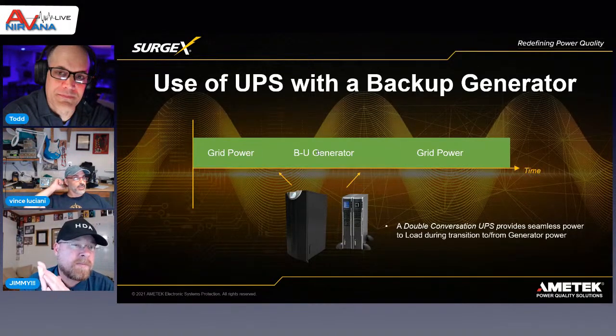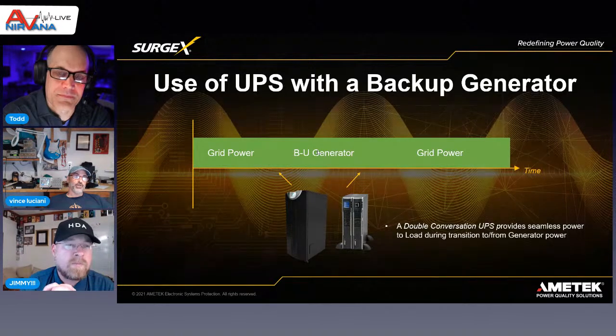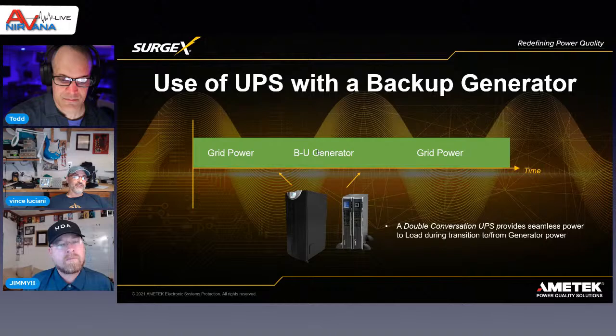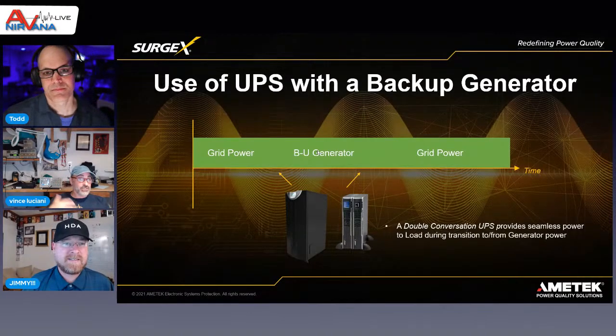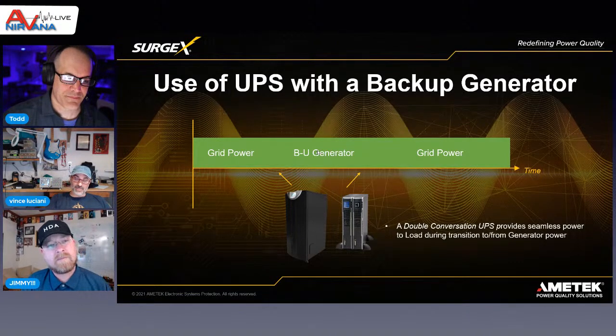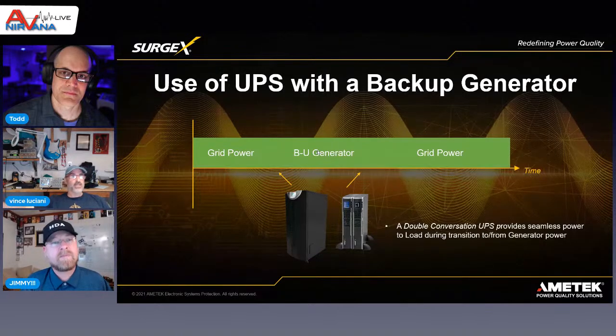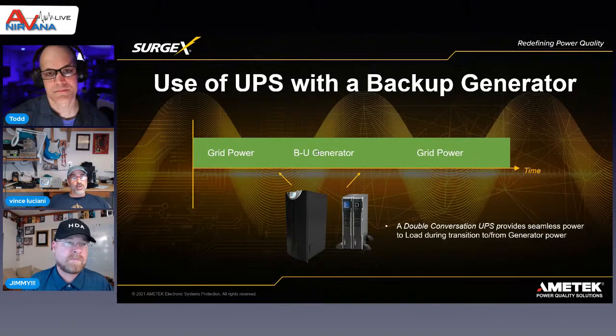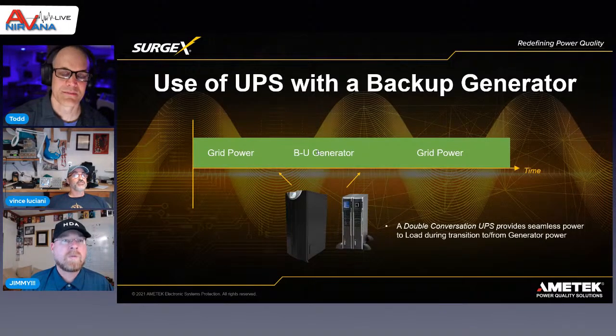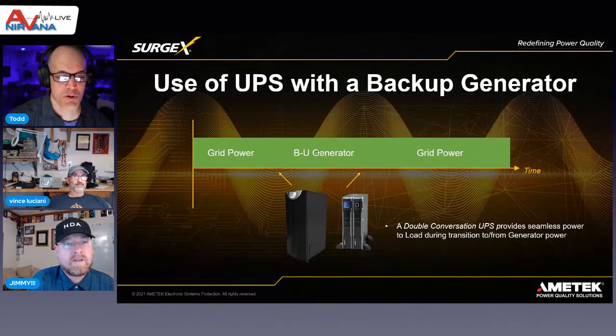Yeah, so the things I would look at: read the label and see what the voltage protection rating is, and make sure—the lowest that UL will put on the voltage protection rating is 330 volts. It's funny, our device has a voltage protection rating of 330, mainly because they didn't know what to do with zero—it's like, okay, the lowest number we got on the chart is 330. They didn't know that people could get lower than that, so we're actually 330 even though we're zero. But look, because there's some that'll be 330, some 400, some 5, 6, 7, 800—get one with the lowest number. The other thing you want to look for is one that has an LED on it that tells you when the surge protection device, or the MOV, is blown up, because there's a lot of them out there that will continue to pass power even if the MOV is blown up. So it turns into basically a glorified power strip.